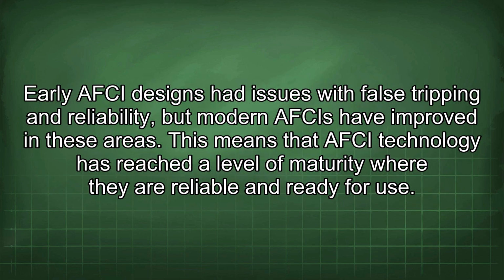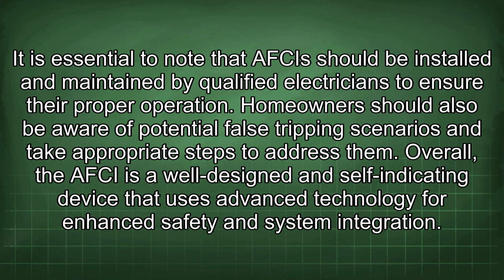Early AFCI designs had issues with false tripping and reliability, but modern AFCIs have improved in these areas. This means that AFCI technology has reached a level of maturity where they are reliable and ready for use. It is essential to note that AFCIs should be installed and maintained by qualified electricians to ensure their proper operation. Homeowners should also be aware of potential false tripping scenarios and take appropriate steps to address them. Overall, the AFCI is a well-designed and self-indicating device that uses advanced technology for enhanced safety and system integration.